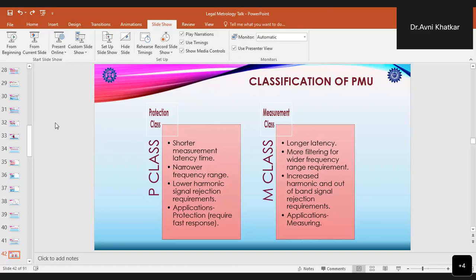However, the M-class PMUs are the measurement class PMUs which are required for applications which deal with measuring. So they have longer latencies, and they require more filtering for wider frequency range requirements. In this, we have increased harmonic and out of band signal rejection requirements, and these PMUs are used basically for measuring applications. So basically PMUs are of two types, P-class or M-class, based upon their application in the grid.